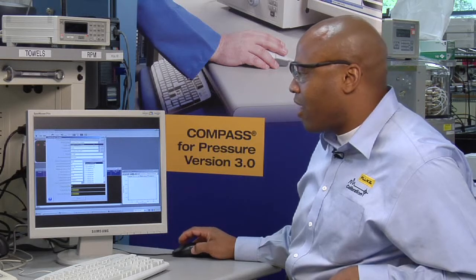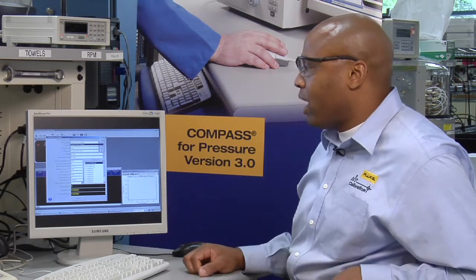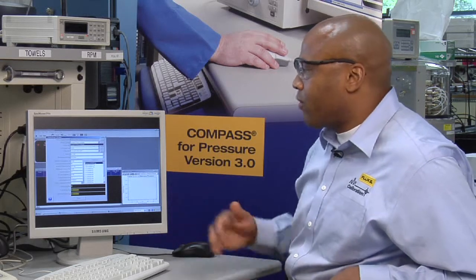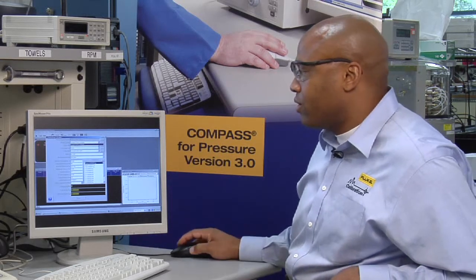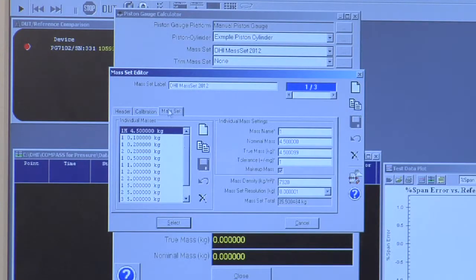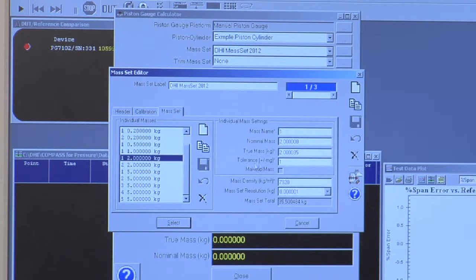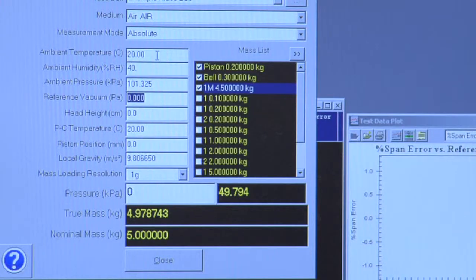In this example I only have one, but for a typical platform you can have several piston cylinders defined. The mass set is also fully customizable, so any number of discrete masses can be created to work with the piston gauge.